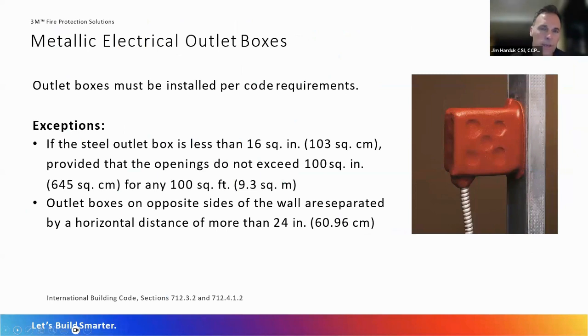And just without getting into a whole lot of code detail right now, but basically, if you have steel outlet boxes that exceed 16 square inches, or if you have a situation where you have over 100 square inches of opening in any 100 square feet of wall section, you're required to protect those outlet boxes. And the way you can do this is by using a putty pad. Also, if you have outlet boxes on the opposite side of the wall, and they are separated by less than 24 inches, you have to use a putty pad or some other type of fire protection on those items as well. Next slide.